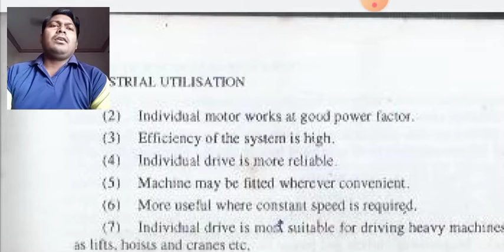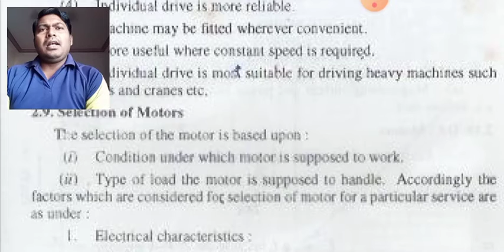Now, the selection of motor. How to select a motor? The selection of the motor is based upon certain conditions. So what are the conditions? The condition under which the motor is supposed to work is the first criterion. The second one is the type of load the motor is supposed to handle. Accordingly, the factors considered for selection of a motor for a particular service are as below. Electrical characteristics: running characteristics, starting characteristics, speed control, and braking characteristics. These four are essential electrical characteristics.